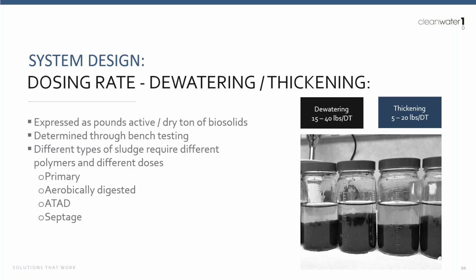It's really important to note that different sludges can require vastly different polymers and vastly different dosages. So a primary sludge is much different than an A2O sludge. Aerobically digested sludge is going to be much different than any of the other ones as well. So really nailing down your specific dosages based on jar testing is really important for the final design. Sometimes during early design, when this information isn't available, we need to make an estimate. There are guidelines. Generally, dewatering is around 15 to 40 pounds per dry ton. The general number that I use when we don't have that jar test information for dewatering is around 25 pounds per dry ton.